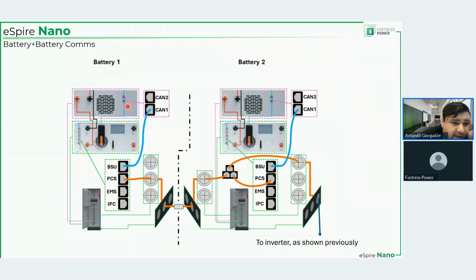And just like before, CAN 1 port of the bottommost module within the battery cabinet connects to the BSU port on the battery control module for both battery cabinets. If you have the third battery, right, you would have the same configuration as here. So battery 3 would connect to battery 2 via splitter. It's just this splitter would not connect to the inverter, obviously, but would connect to the splitter within battery number 1. And that splitter would have PCS connected to it. Output from the second splitter, responsible for batteries 2 and 3, would connect here. PCS of the battery number 1 would connect here, and then this cable would connect to the inverter. And again, we are using the middle knockout here.